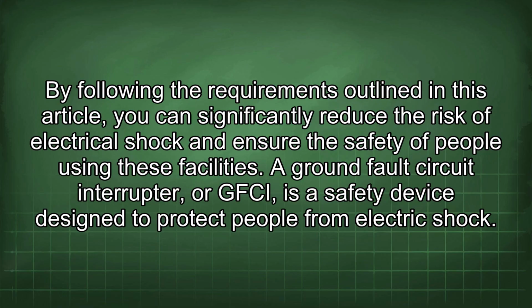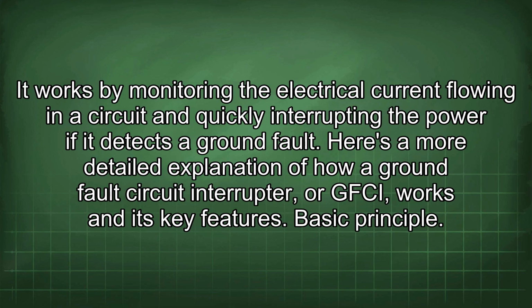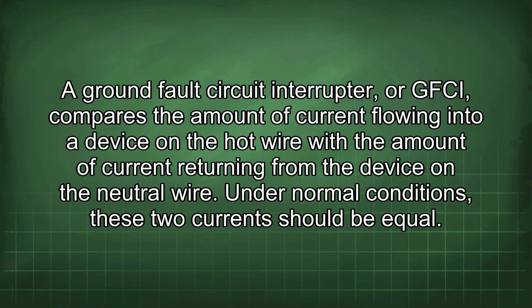A ground fault circuit interrupter, or GFCI, is a safety device designed to protect people from electric shock. It works by monitoring the electrical current flowing in a circuit and quickly interrupting the power if it detects a ground fault. Here's a more detailed explanation of how a GFCI works and its key features. Basic principle. A GFCI compares the amount of current flowing into a device on the hot wire with the amount of current returning from the device on the neutral wire.